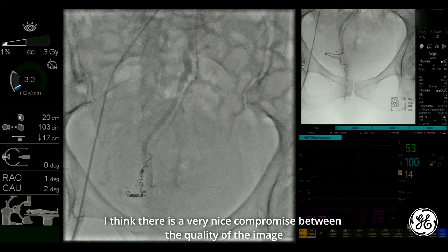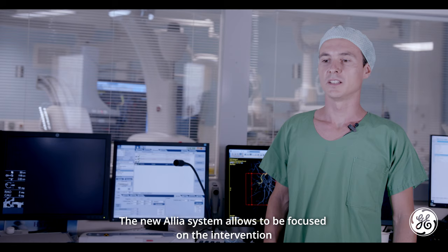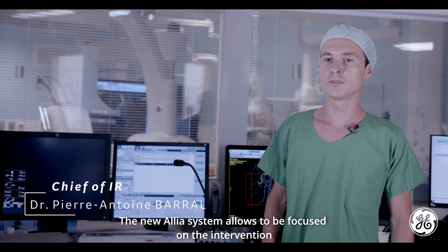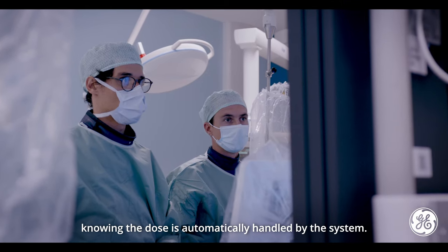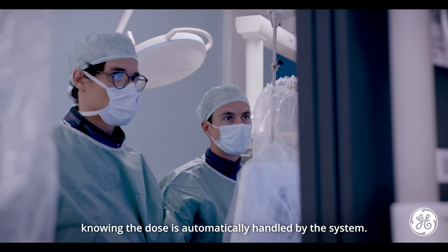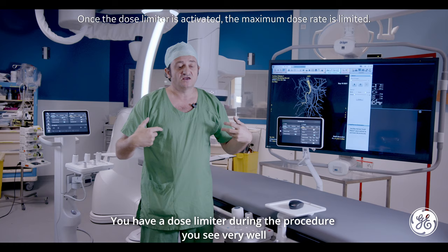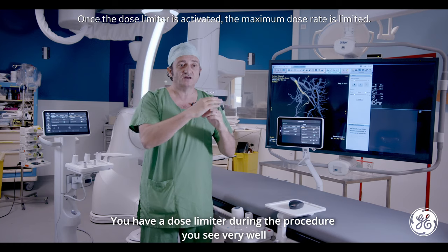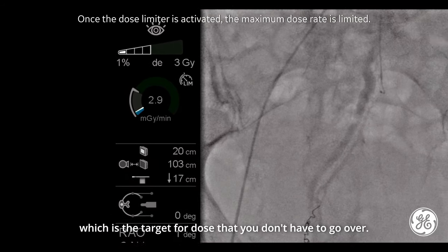I think there is a very nice compromise between the quality of the image and the dose exposition. The new Allia system allows you to be focused on the intervention, knowing the dose is automatically handled by the system. You have a dose limiter. During the procedure, you can see very well which is the target for the dose that you don't have to go over.